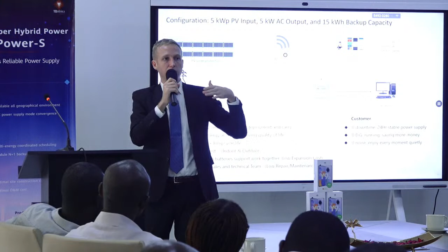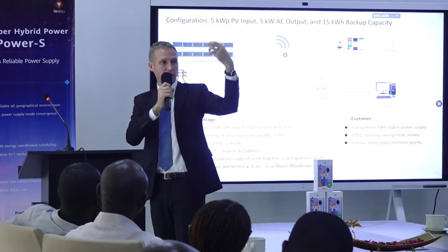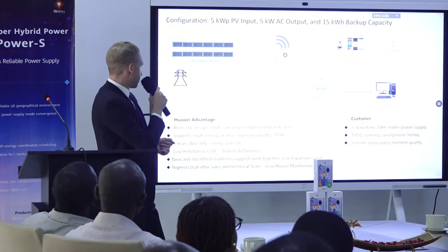It has 2 MPPT inputs, which means if you don't have a directly south-facing roof -- because with solar panels, you want your panels to face the equator to maximize sunlight -- but a typical household doesn't have a directly south-facing roof without shade, usually it's more complicated than that. So this system allows you to pick 2 strings, where maybe you want to harvest sun from the east and harvest sun from the west. This system allows you to do that, so you maximize the irradiance, the sunlight that you do have.